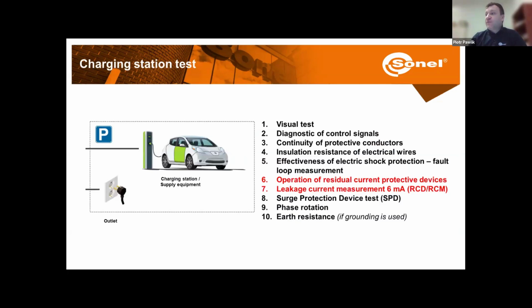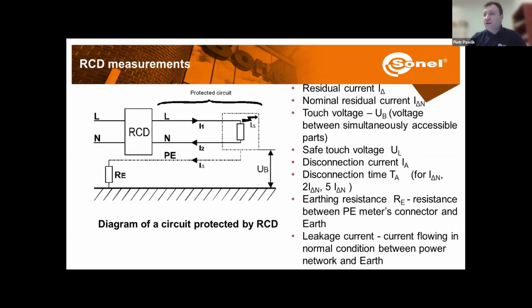Okay, then the next measurements will be RCDs and RCMs. Here is how the RCD works: the device is powered through a phase channel or channels. Returning current is on the neutral channel. If those currents are about the same, then the RCD is not going to work. But in case we have some leakage currents, some residual currents flowing through the PE channel or through any other way, then there will be a difference between current on the phase and the neutral channel, and the RCD is going to work. So the parameters that we can check here will be the value of this residual current, the disconnection time, touch voltage, so voltage to ground, or resistance to ground.